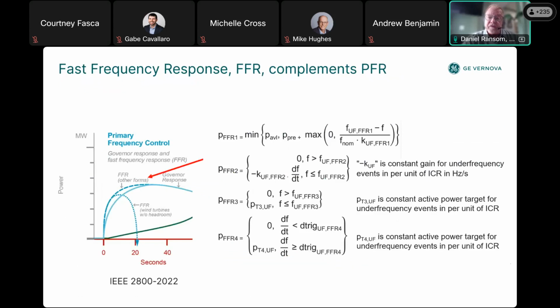Along with primary frequency response, there is fast frequency response. This is during the arresting phase of the frequency excursion. FFR is similar to PFR, but it's faster, and it has a droop percentage of 1%, providing a 100% change in power for a 1% change in frequency. FFR is active only to the applicable frequency nadir point, to where the arrow is pointing here in the slide. The FFR step response time capability has to be within 1 second.